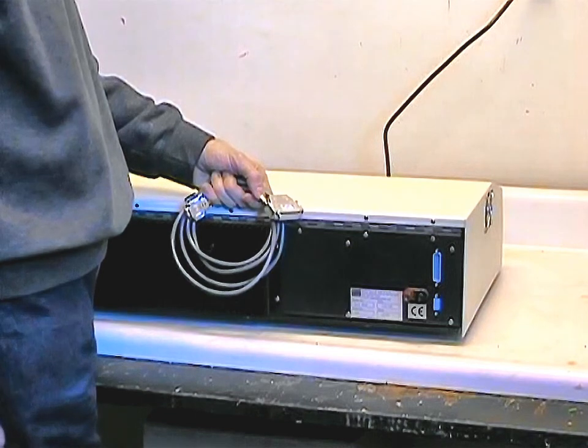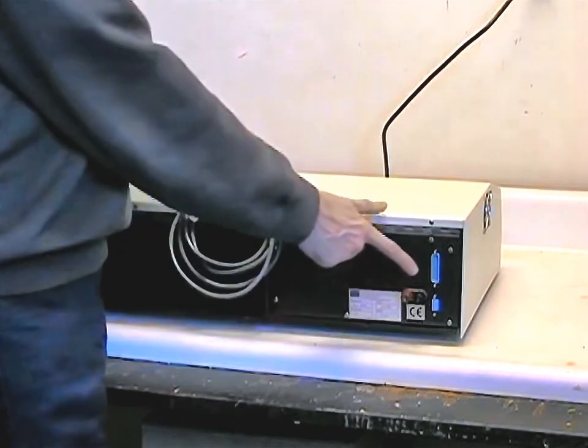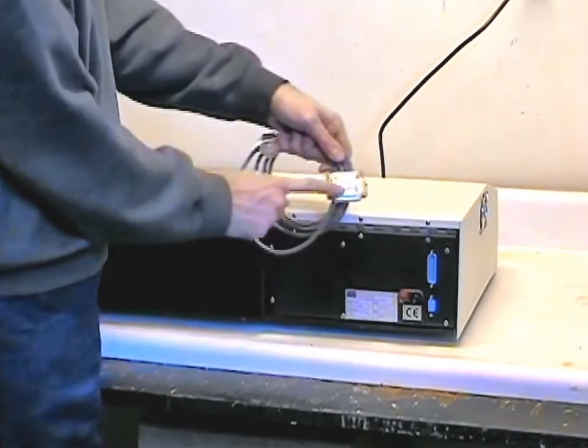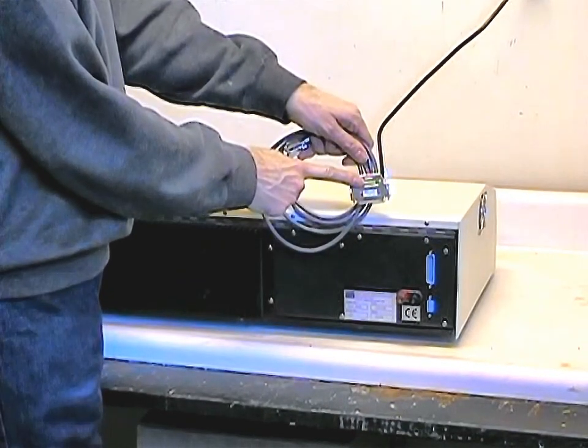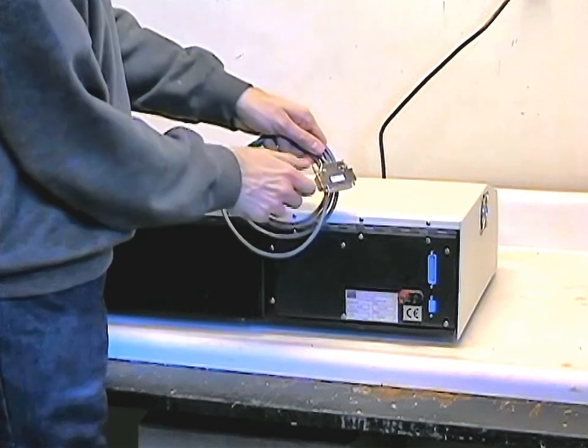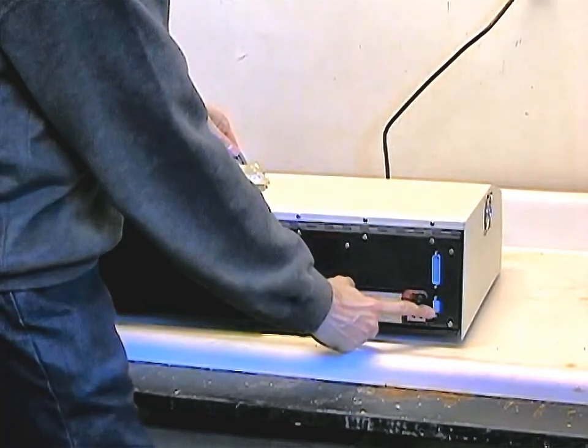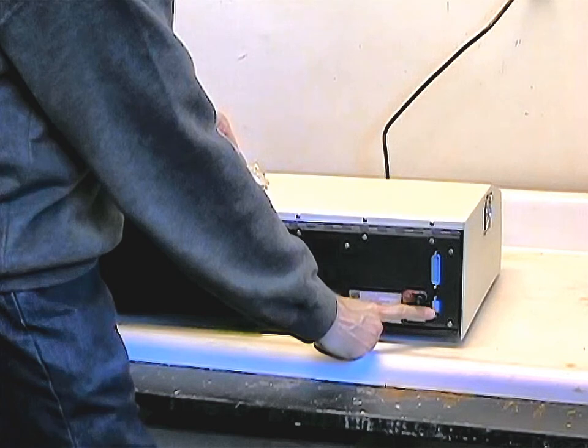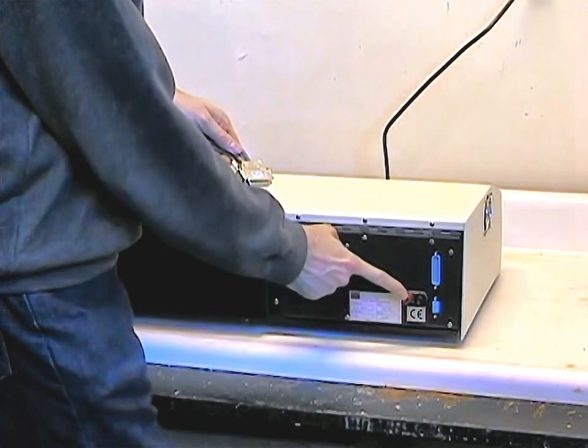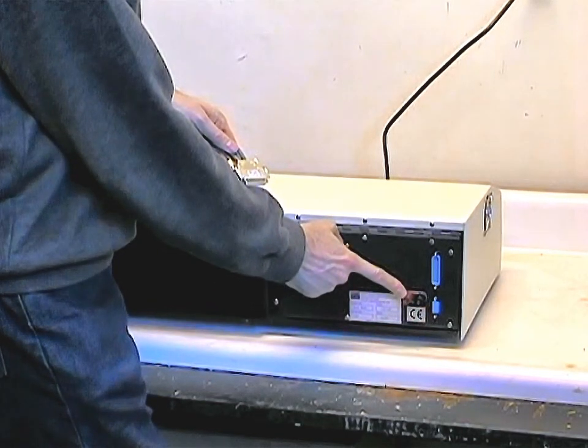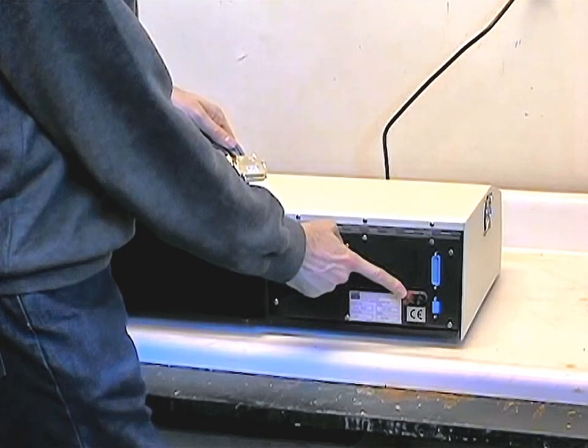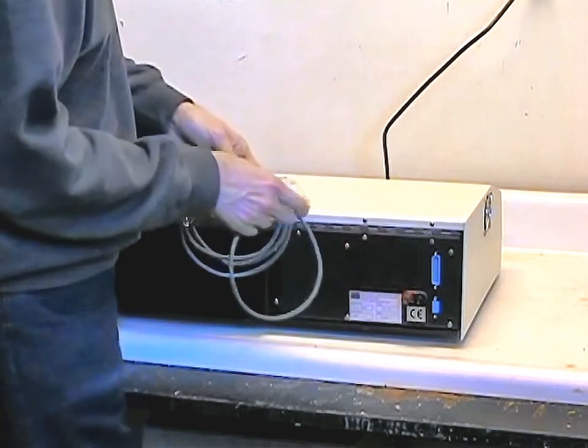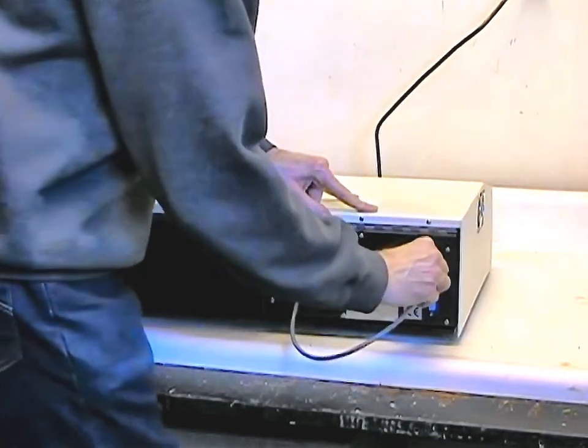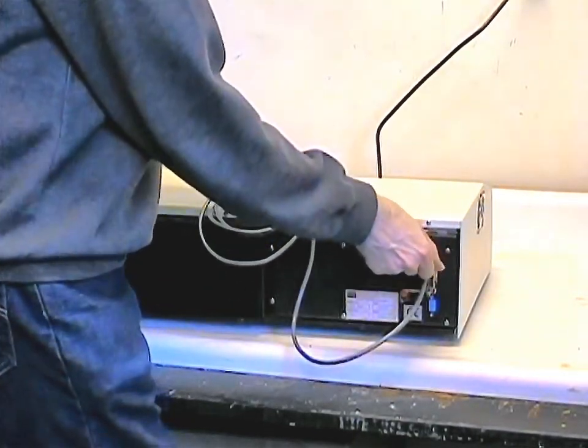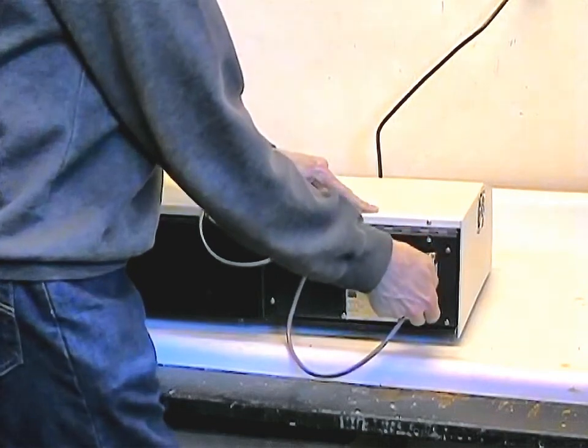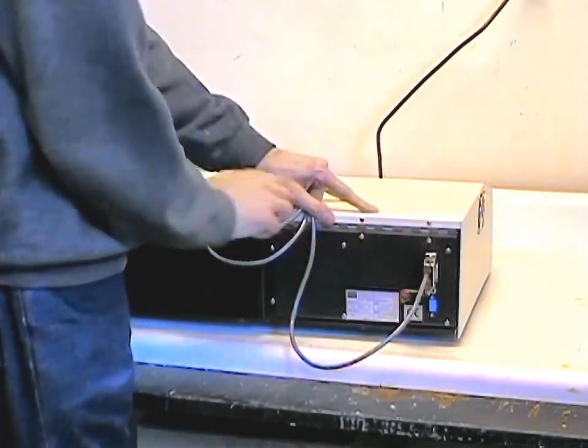On the back of the M500, we can see our 25-pin serial port connector, which is used to interface to a PC. Buck Scientific also has a specifically configured strip chart recorder, which uses a 9-pin D connector shown beneath that. And for other analog operations, we have standard banana plug connections with a 0 to 1 volt output. Again, be sure that the 25-pin serial connection is tight, as this will ensure good data quality and avoid dropouts of the data packets as they're sent from the instrument to the PC.